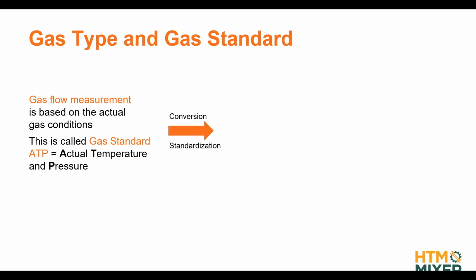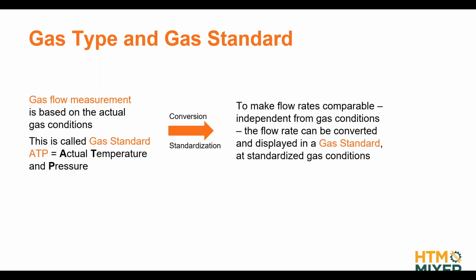But then, in order to standardize or compare flow rates, we can convert them into different gas standards. So how much flow would that be, for example, if my temperature would be that many Fahrenheit and the humidity would be different than the actual humidity of the gas that I measure right now. This is all convertible mathematically with some formulas in the background. So for now, let's make sure we understand this process is what we call gas flow displaying. It's different what we measure and what we finally display on our gas flow analyzer. So that was now the background.